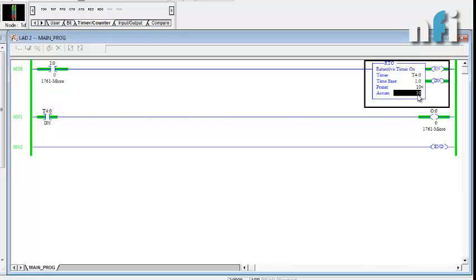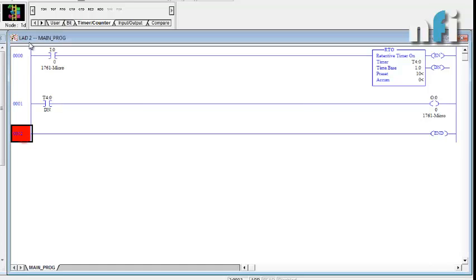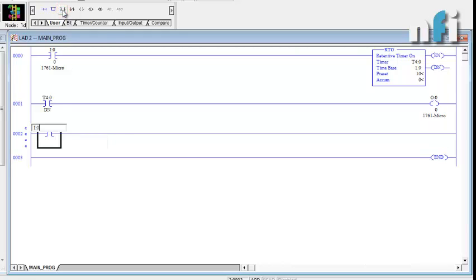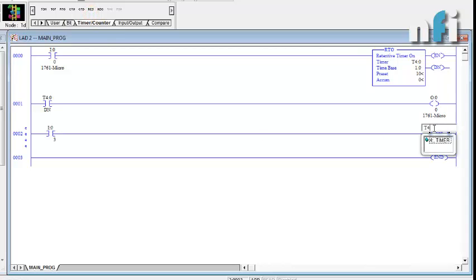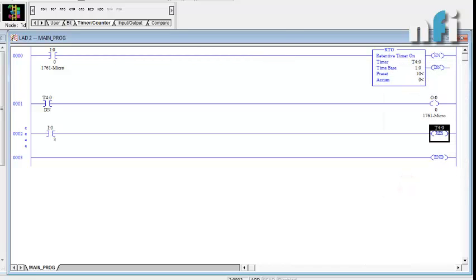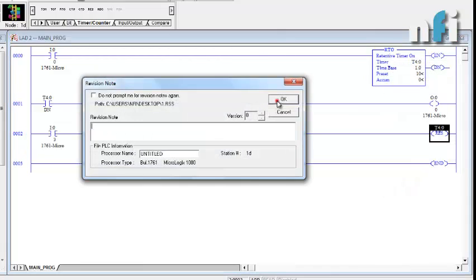This is called a retentive timer — it retains and holds the time and will not reset itself. To reset it, we can use a reset command. I'll add a rung with button I:0/3 and use a RES (reset) command with address T4:0. This will reset the timer. Let's download this program.